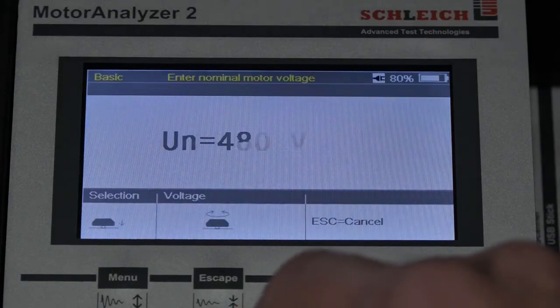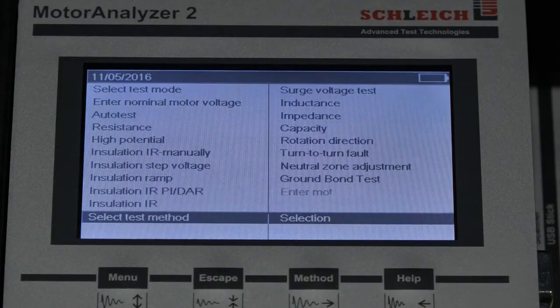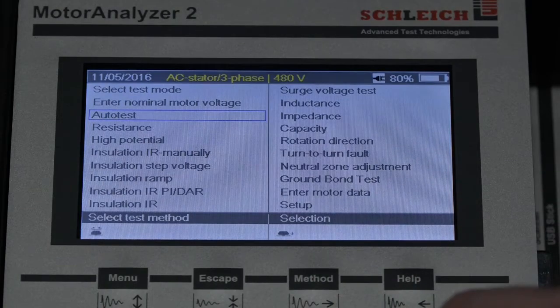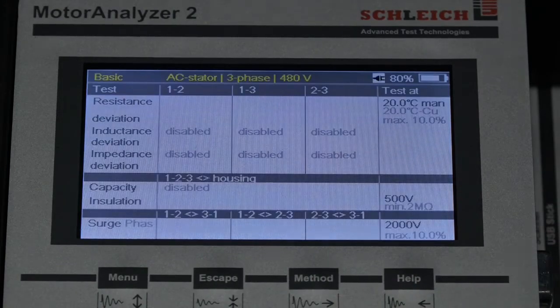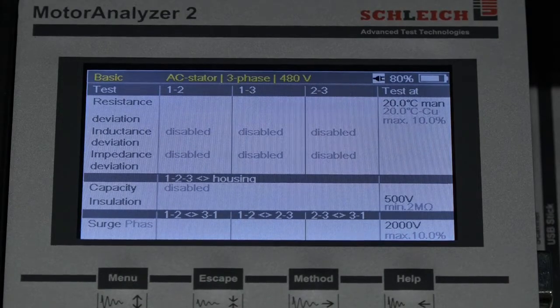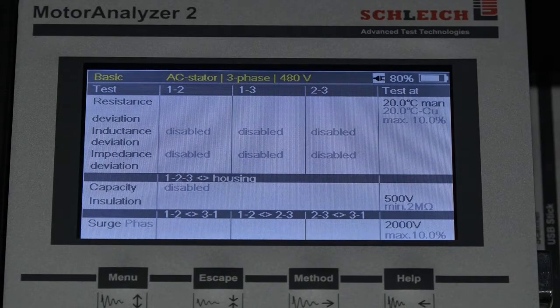Again, it will ask us for a voltage. This is a 480 volt stator. Select that. Select the auto test. And again, it's queued up the test that we're going to run. To start the test, we'll press the start-stop button. There we go. So now we're running the resistance test. Again, 1 to 2, 1 to 3, 2 to 3, and then we calculate a deviation. When it's done with the resistance test, we'll step right on into an insulation resistance test.